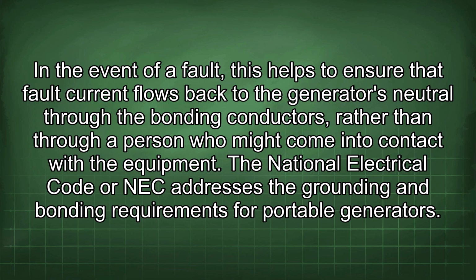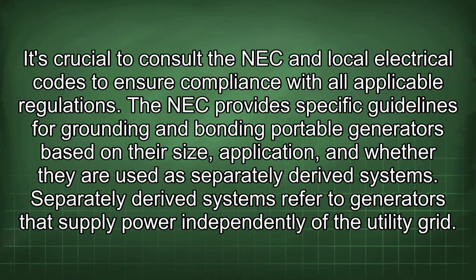The National Electrical Code or NEC addresses the grounding and bonding requirements for portable generators. It's crucial to consult the NEC and local electrical codes to ensure compliance with all applicable regulations. The NEC provides specific guidelines for grounding and bonding portable generators based on their size, application, and whether they are used as separately derived systems. Separately derived systems refer to generators that supply power independently of the utility grid.